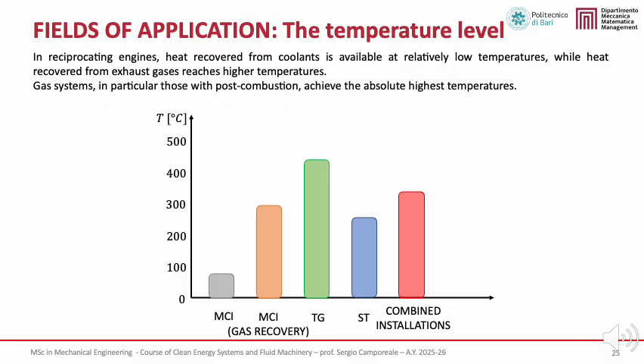Finally, combined installations, where different technologies are integrated, allow heat recovery over a wider temperature range. This increases system flexibility and enables the supply of different thermal users simultaneously. Overall, this slide highlights that the quality of recovered heat, not only its quantity, is crucial for selecting cogeneration technologies and for matching energy supply with thermal demand.